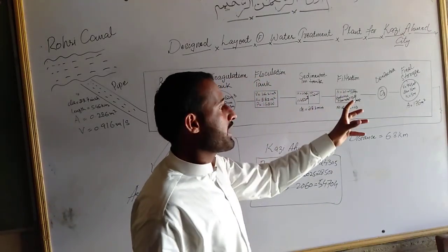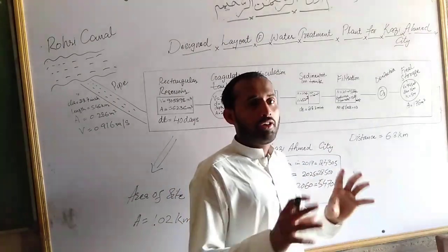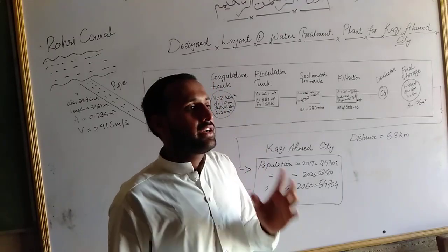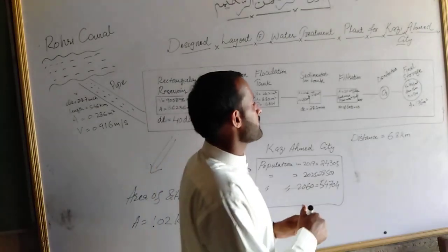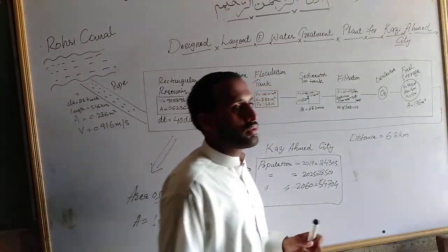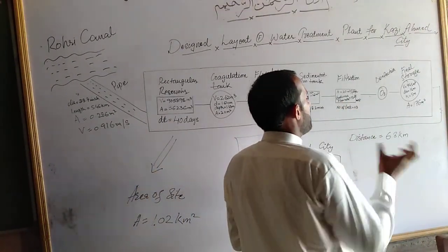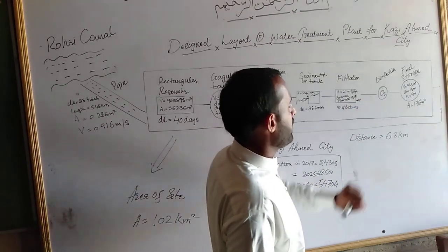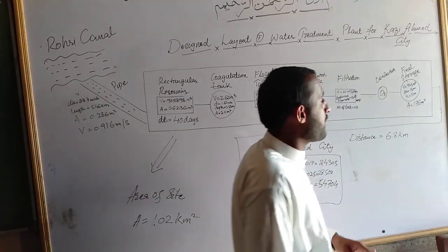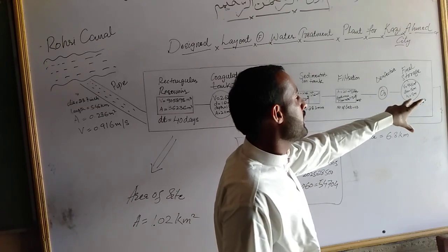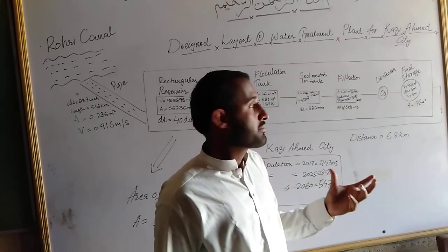When filtration is carried out, there is an accumulation of solids on the filter media, so it gets accumulated, and the time comes when it is choked. So some sort of backwash is also required, so that the filter media is cleaned up. The flow rate for the backwash water is 50 meter cube per minute. And then when water is filtered, there can be some microorganisms or bacteria present in the water. So we have to disinfect it, meaning we have to inactivate those microorganisms from the water.